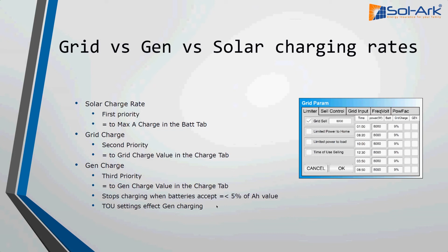A few more things to note here: if you are using a generator connected to the Sol-Ark's grid input breaker, you need to select this box here in Sell Control called Gen Connect to Grid Input. That's to tell the inverter to expect a generator so that we don't try to sell back to it. Because as you guys probably know, there can only be one winner in that situation, and we prefer not to get into that. Also, to improve the generator connectivity, because a lot of generators tend to have, let's say, not the cleanest power usually, we recommend that you change the inverter settings to generator standard mode, which is over here in Sell Control, and then also going over to your grid input tab and widening the range of frequencies that are acceptable for the Sol-Ark before it disconnects. So usually you can do 55 to 65 hertz instead of the default values, and that'll improve the connectivity to a generator.